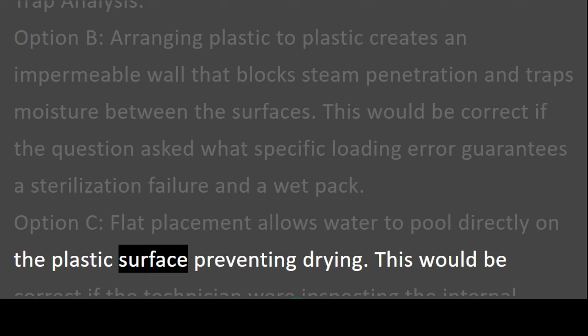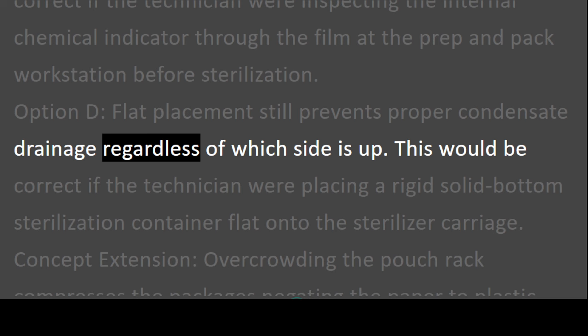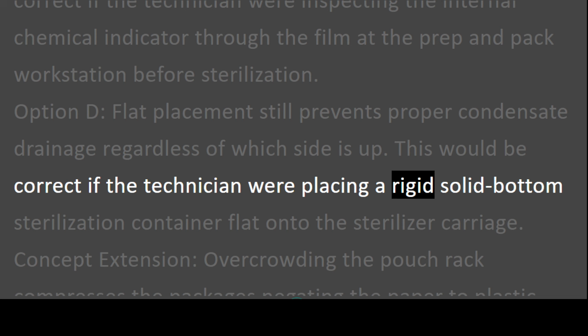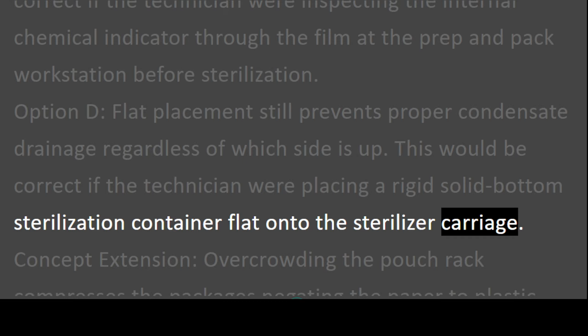This would be correct if the technician were inspecting the internal chemical indicator through the film at the prep and pack workstation before sterilization. Option D: flat placement still prevents proper condensate drainage regardless of which side is up. This would be correct if the technician were placing a rigid solid-bottom sterilization container flat onto the sterilizer carriage.